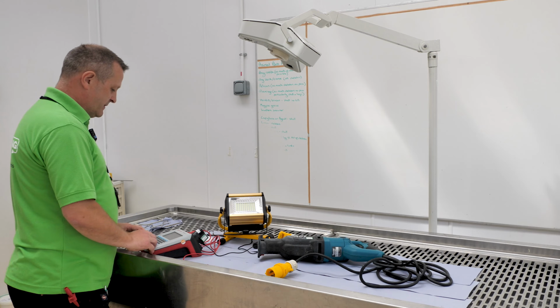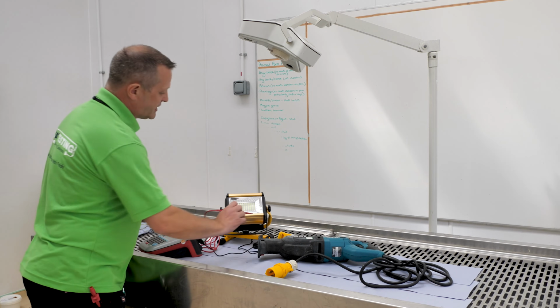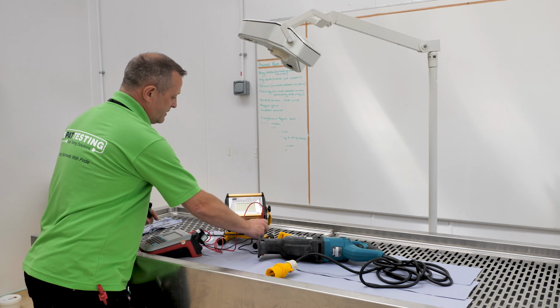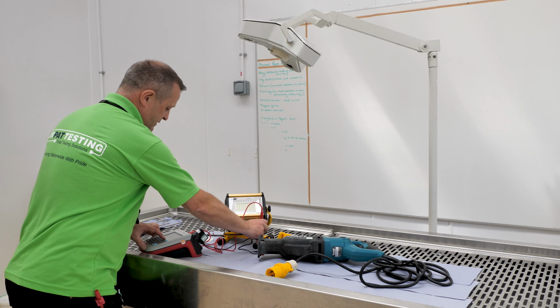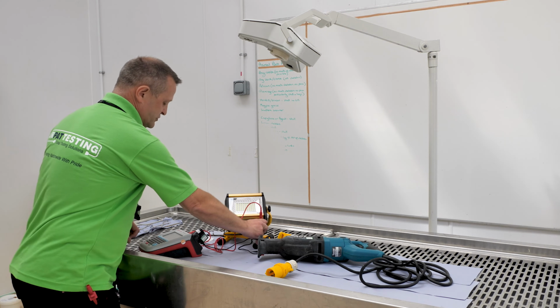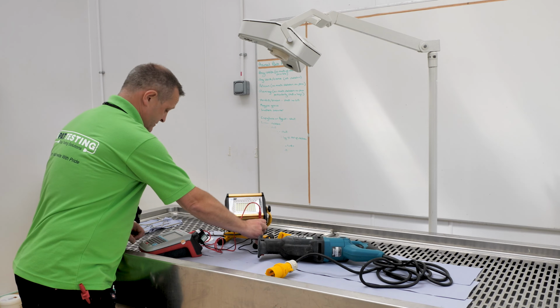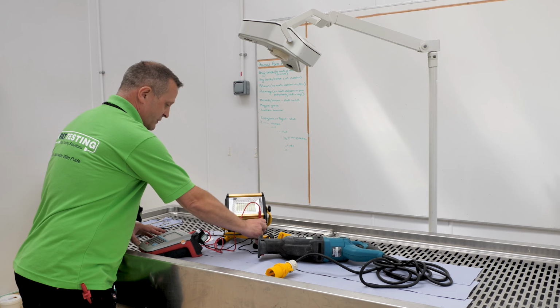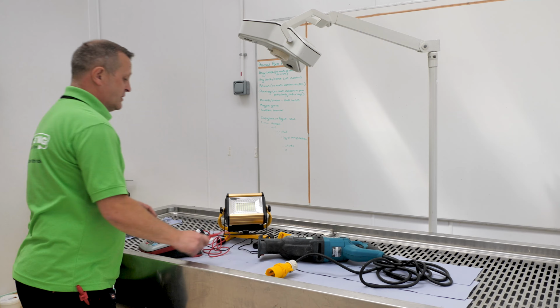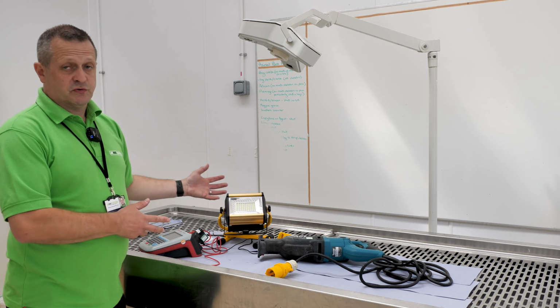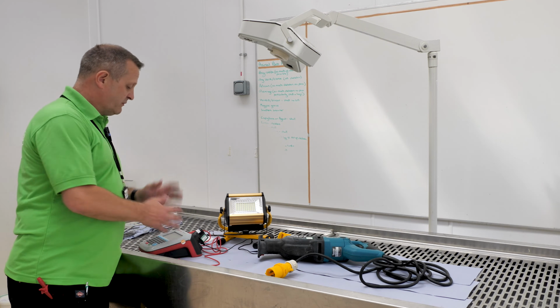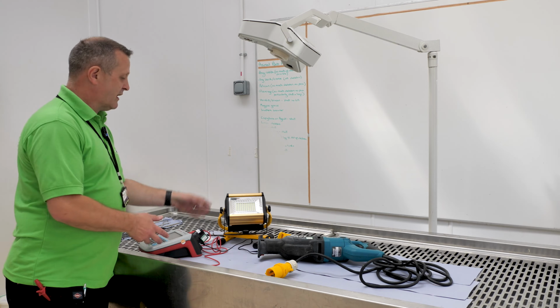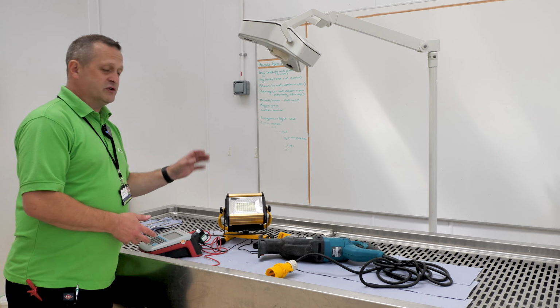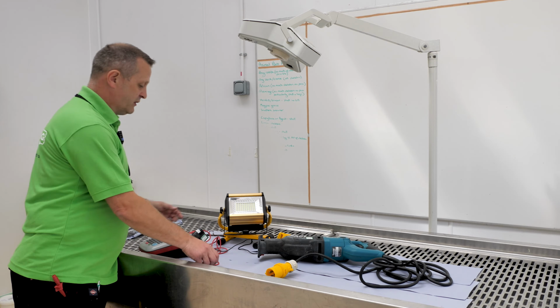Plug into the machine, select the correct test, attach the probe to part of the metalwork, exposed metal, and then we'll just go through an insulation resistance test, and that's showing it's perfectly fine. As with every test, we've already conducted the visual inspection, we fill in the details, we record that, and we attach a label onto a nice clean part of the appliance.